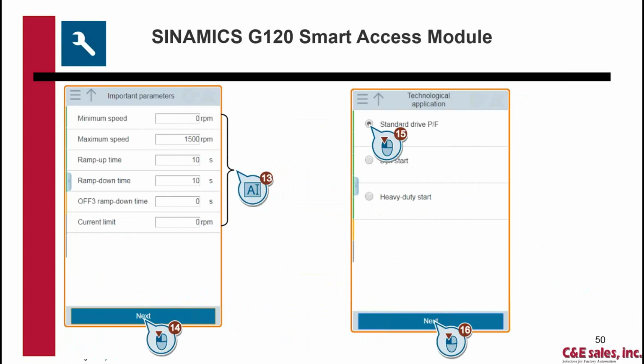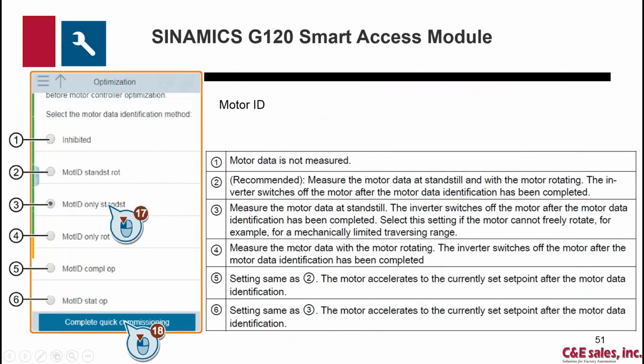So again, that's our old setup. There's some more parameters: minimum speed, max speed, ramp up time, downtime. Then we get to pick standard drive, dynamic start, or heavy duty start. And that's just more, what kind of loads on the drive and the motor. Next is optimization. We can inhibit optimization. Motor ID at standstill. Motor ID only at standstill, only at rotate. The first was standstill and rotate.